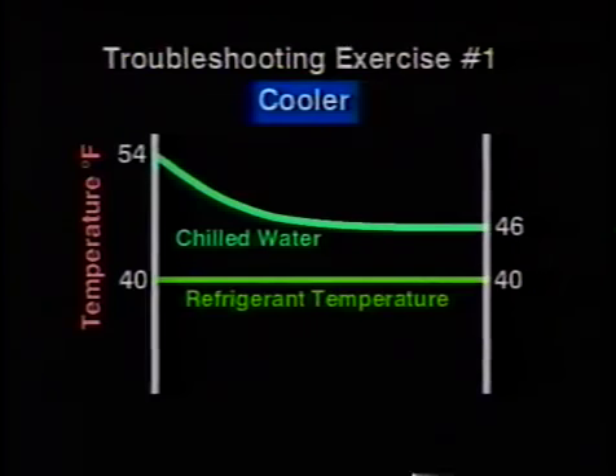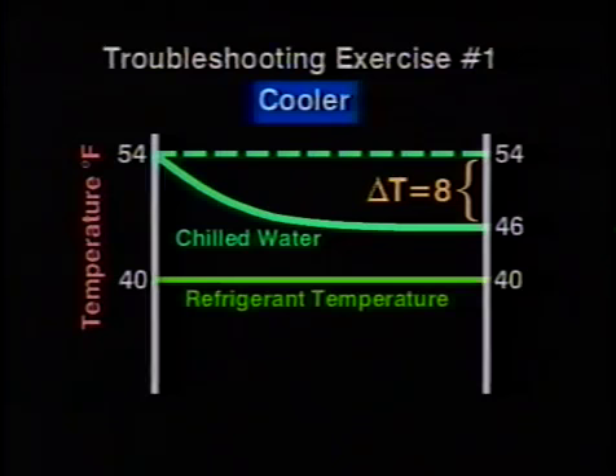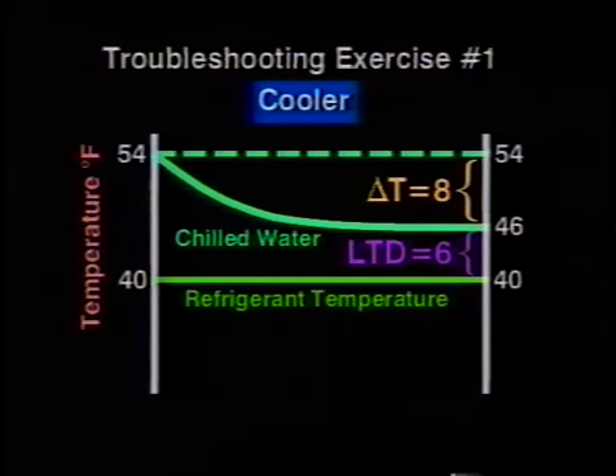Okay, let's see how well you've done. The chilled water entering is normal, but the leaving chilled water is 2 degrees Fahrenheit high, giving us a delta T of only 8 degrees. The LTD is 6 degrees, an indication of no resistance to heat transfer.